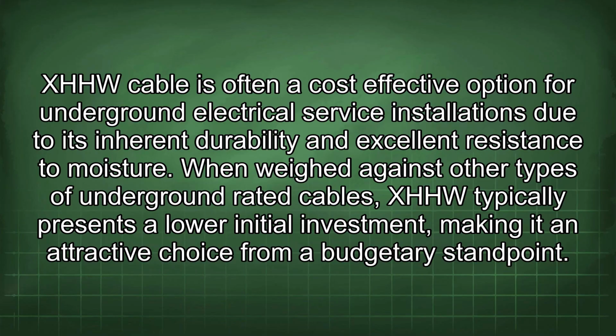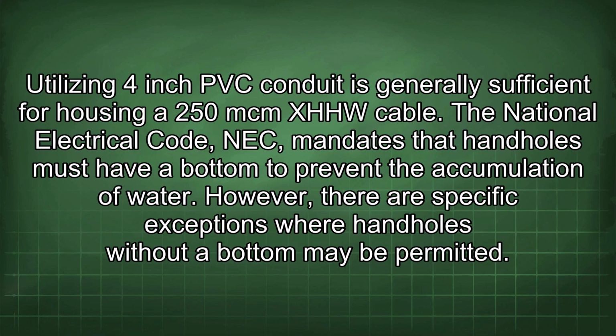XHHW cable is often a cost-effective option for underground electrical service installations due to its inherent durability and excellent resistance to moisture. When weighed against other types of underground rated cables, XHHW typically presents a lower initial investment, making it an attractive choice from a budgetary standpoint. Utilizing 4-inch PVC conduit is generally sufficient for housing a 250 mcm XHHW cable.